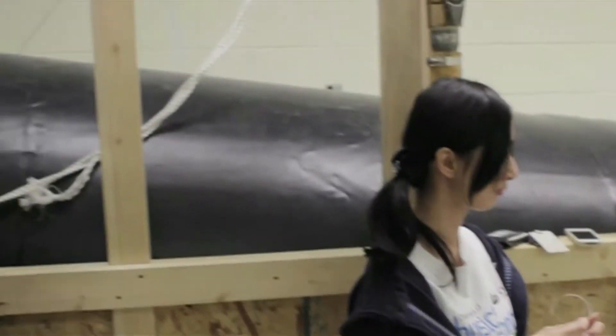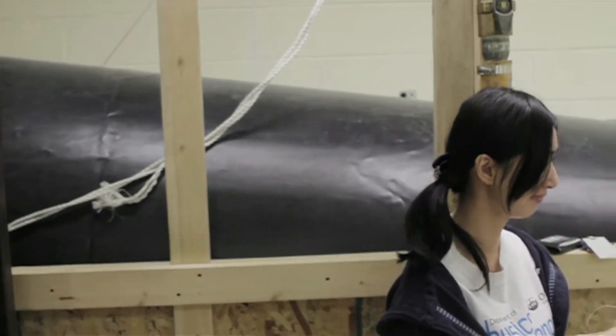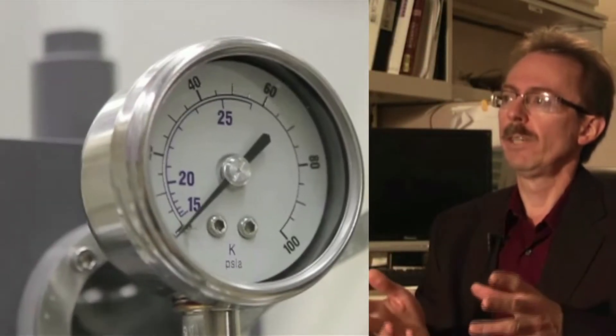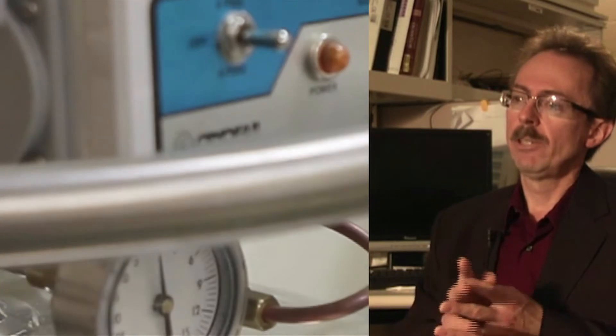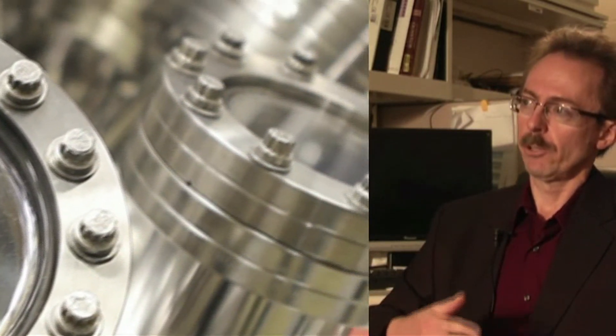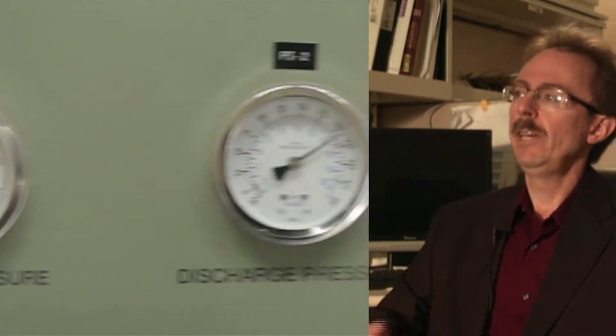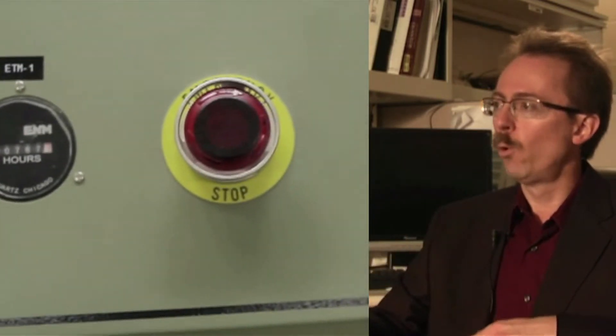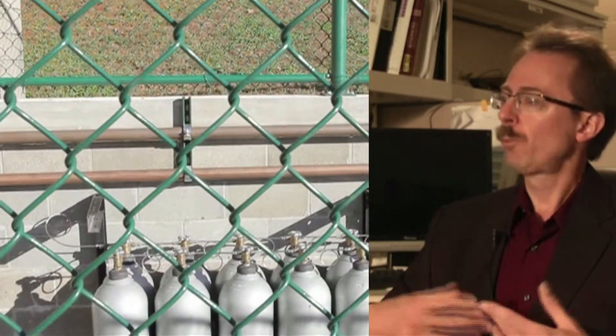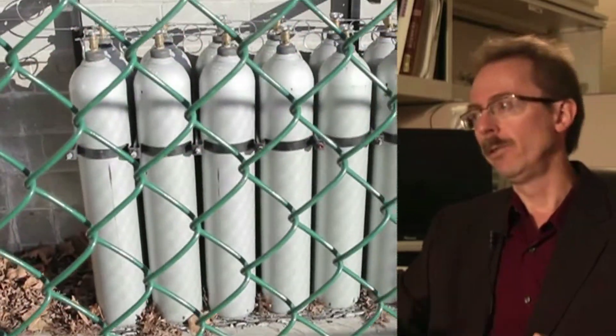Basically when the experiments are running in the labs, liquid helium is becoming gaseous helium. What we're doing here in this building with this liquefier recovery system is being able to generate the liquid helium necessary to run the scanning tunneling microscopes at very low temperatures, and then recovering the boiled off helium gas, which is returned back to this building, which we then reprocess and reconvert back into liquid helium.